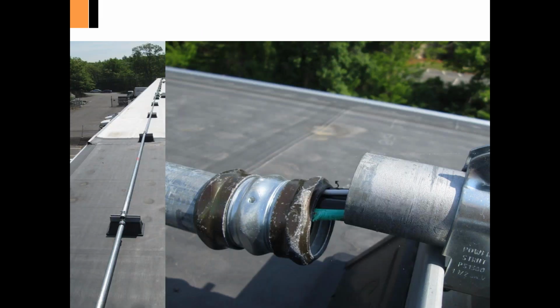This next photo, the scenario was slightly worse, where we had expansion and contraction. And this one, again, a long run, probably over 200 or 300 feet, if I remember correctly. But we also noticed, if you look at the different color rooftop here, I believe it crossed a building expansion joint as well. So this may or may not have been from thermal. This could have been from the normal building expansion, which would require that fitting. In this case, the conduit pulled out and started to cut into the ground wire, luckily, and we started to see some insulation cut on the DC conductors.